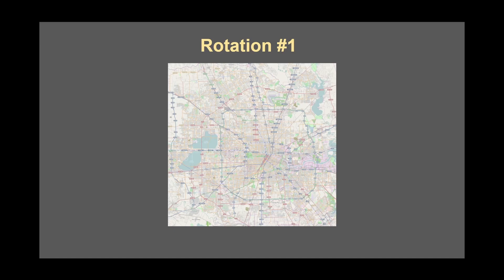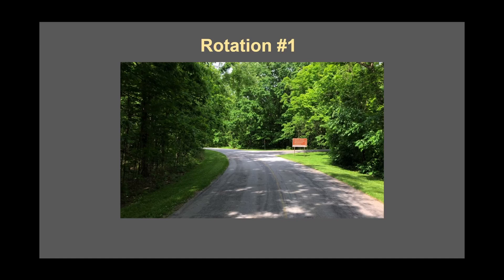Number three, DC schematics. The one-lines and three-lines are used to build the DC schematics. Number four, the wiring. The wiring is built directly from the schematics — both AC and DC — and is the most detailed drawing. This would be the ground-level street view in the map example. So when I say I did a wiring QA, I did point-to-point checks and verified that the wiring matched the schematics. Honestly, I kind of enjoyed it. And now that I'm building whole P&C packages, I can appreciate the detail needed to give the client quality work.